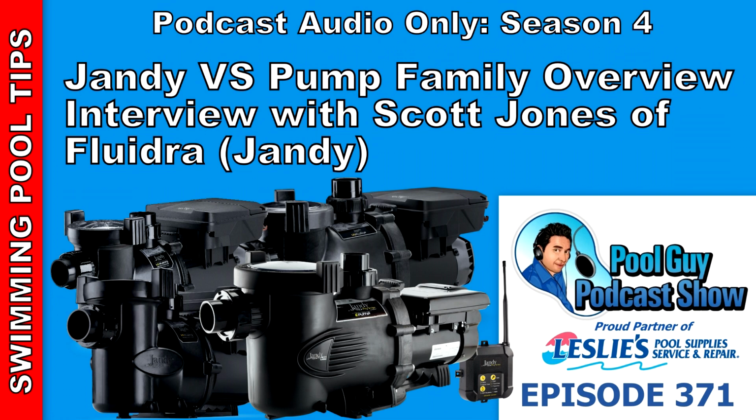Okay, and then before I end, is there any caution about the auxiliary relays? What would be something that you couldn't connect to it? One thing that people ask a lot, and it's not that you technically can't do this, but we recommend against it. People always say, "Can I run my heater through the auxiliary relay?" And I know that people do it. We actually train the correct way to do it, and we have something called Zodiac Academy where they discuss the best way to do this. But one of the risks with a heater is, when the heater is no longer producing heat, you typically still want flow going through it to allow it to cool down.